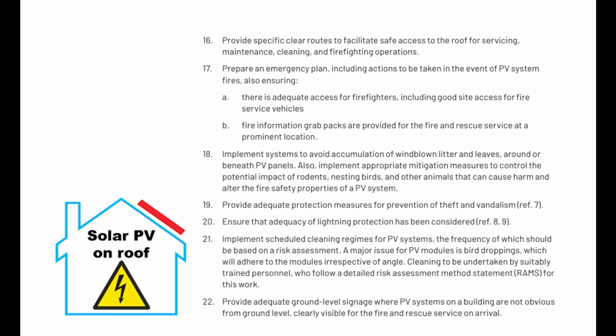Implement scheduled cleaning regimes for PV systems, the frequency of which should be based on a risk assessment. A major issue for PV modules is bird droppings, which will adhere to the modules irrespective of angle. Cleaning should be undertaken by suitably trained personnel who follow a detailed risk assessment method statement, or RAMS, for this work.